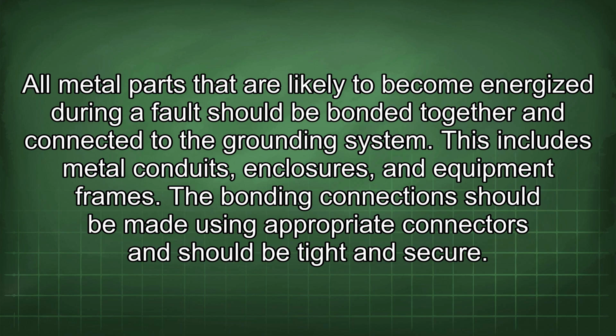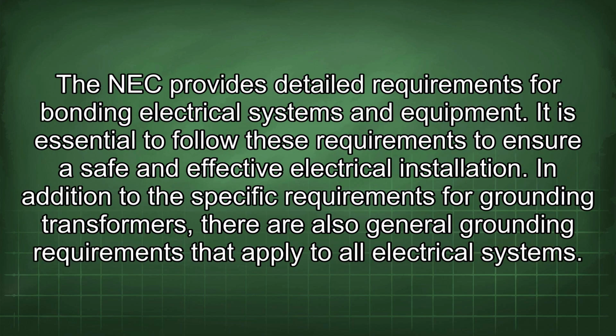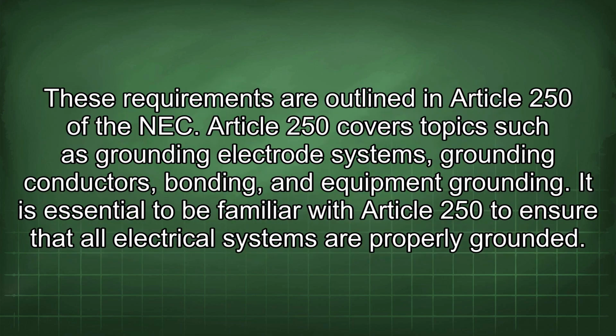The bonding connection should be made using appropriate connectors and should be tight and secure. The NEC provides detailed requirements for bonding electrical systems and equipment. It is essential to follow these requirements to ensure a safe and effective electrical installation. In addition to the specific requirements for grounding transformers, there are also general grounding requirements that apply to all electrical systems. These requirements are outlined in Article 250 of the NEC. Article 250 covers topics such as grounding electrode systems, grounding conductors, bonding, and equipment grounding. It is essential to be familiar with Article 250 to ensure that all electrical systems are properly grounded.